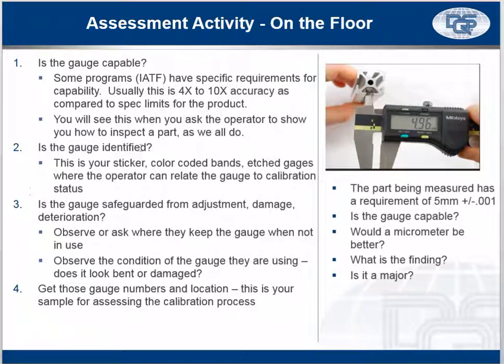Is the gauge identified? So this is where you're looking for your stickers, color-coded bands. So maybe they put a yellow mark on this, and that means it has to be calibrated every January. Or etched gauges, where the operator can relate the gauge to a calibration status. So in a very oily environment, the stickers don't stay on or they get damaged. So they'll etch a gauge number in, and then they'll have a list of gauges and when they're supposed to be calibrated.